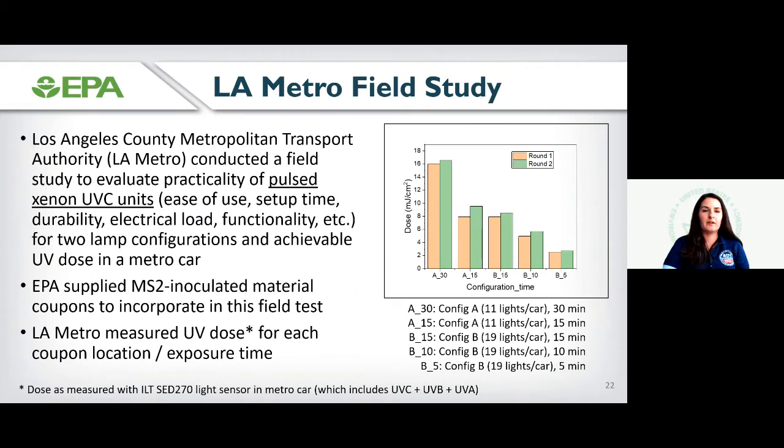As Odions mentioned, we've been collaborating closely with LA Metro throughout the pandemic, looking at evaluating different types of disinfection technologies that could be implemented in different subway cars or buses. And LA Metro is particularly interested in using the pulse xenon light that Lucas has touched on earlier today, and in particular they were interested in evaluating some practical considerations in using these lights as part of routine disinfection practices, such as how easy it was to bring the lights on and off of a subway car, as well as how the electrical load was impacted, how the lights held up from a durability standpoint, and so on.